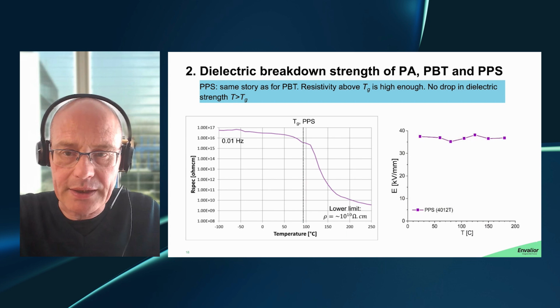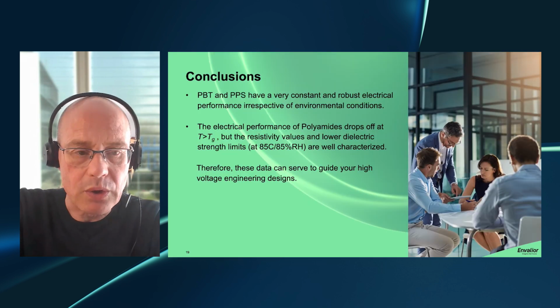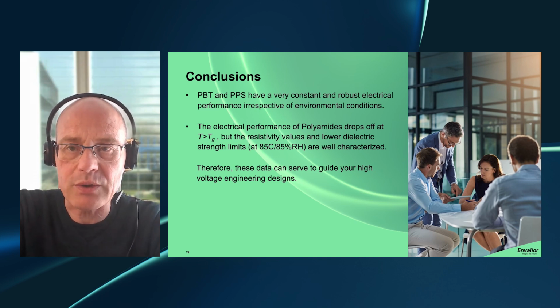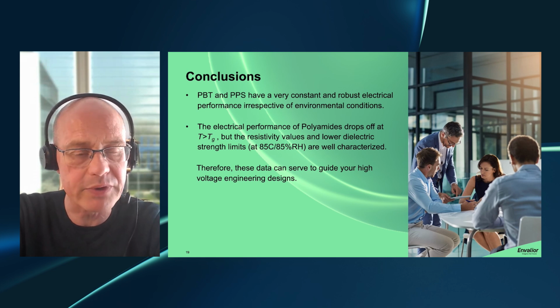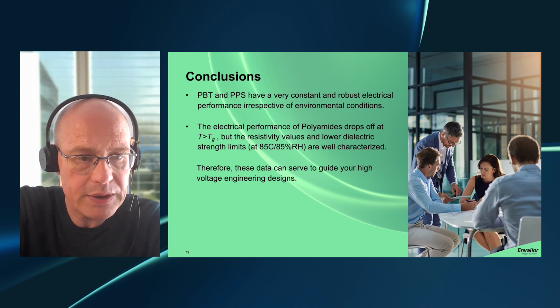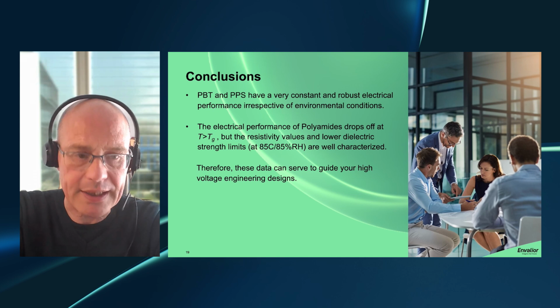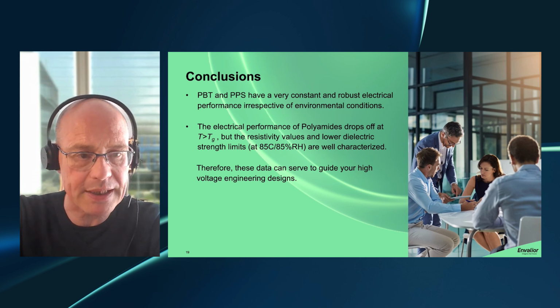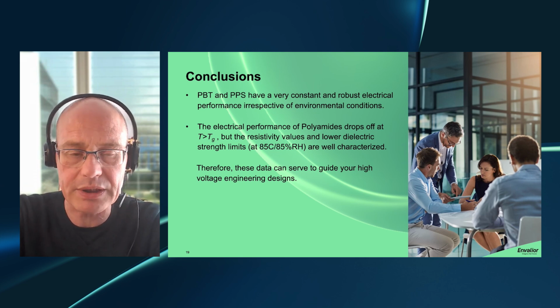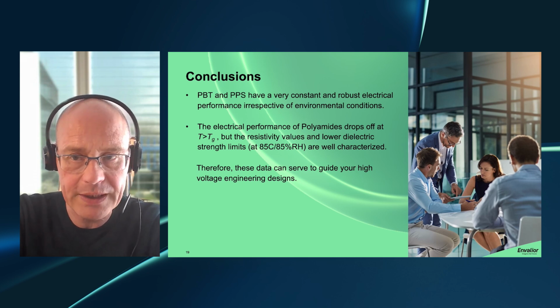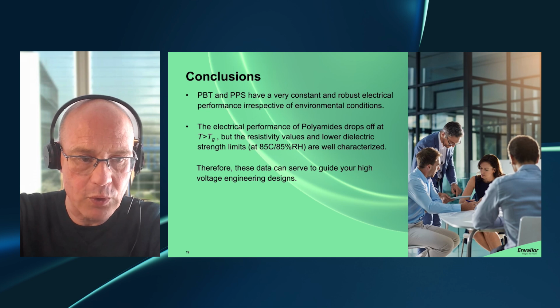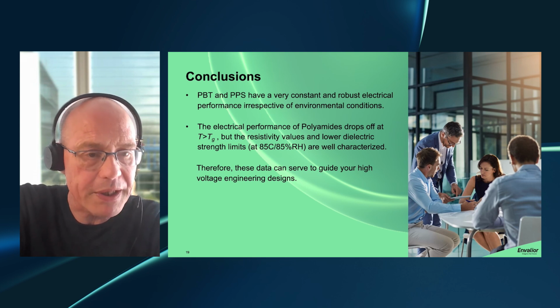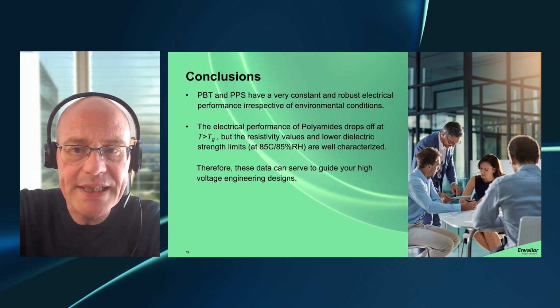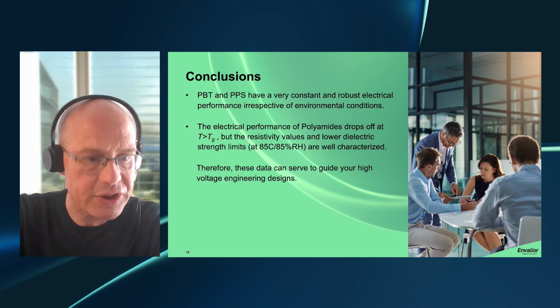Now, this brings me to the concluding slide. What we have shown is that for PBT and PPS, there is very consistent, robust electrical performance, and it is really irrespective of the environmental conditions used. For polyamide, it's also clear, and that goes for all polyamides, that there are drops in electrical properties and breakdown strength above the glass transition temperature, but we have characterized the, let's say, lower strength limit very carefully, and they are very well understood. And therefore, if you choose to use polyamides in your high voltage engineering applications, maybe because of the superior mechanical properties of these products, you can use these data to guide your high voltage engineering designs.